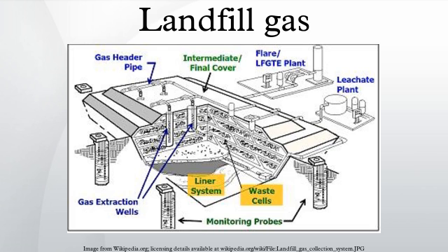The landfill gas can also be sold off-site and sent into natural gas pipelines. This requires the gas to be processed into pipeline quality by removing the water, carbon dioxide, nitrogen, hydrogen, oxygen and any other trace contaminants. Once in the general supply of natural gas, it can be used at power plants producing electricity or in home boilers. Landfill gas can also be used to evaporate leachate, another byproduct of the landfill process. This displaces another fuel that was previously used for the same thing.